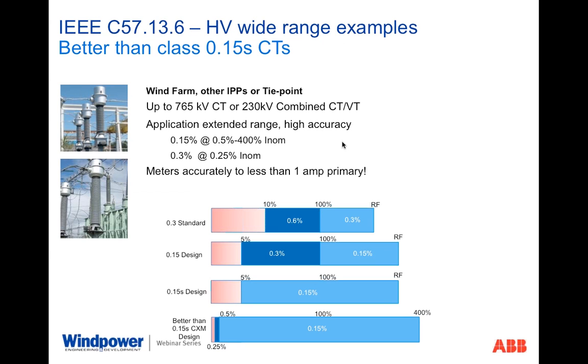Now, when you look at the better than 0.15 class current transformers stacked up against the other classifications, you can see here that the range is absolutely nearly complete across the entire measurement performance range. Compared to the others, it really makes the others pale in comparison. So the important point to take away from this slide is metering accurately currents down to less than 1 amp primary, because that may be what you have in terms of your reverse power. But keep in mind, for the reverse power, you have to consider all of the loads connected and make sure that you accommodate whatever's going to be the application current going back in for reverse power, including your losses in the power transformers that have the generator step up.